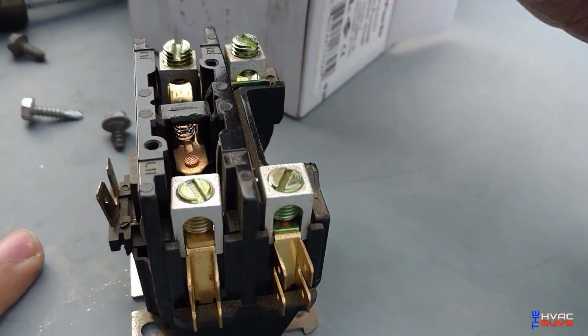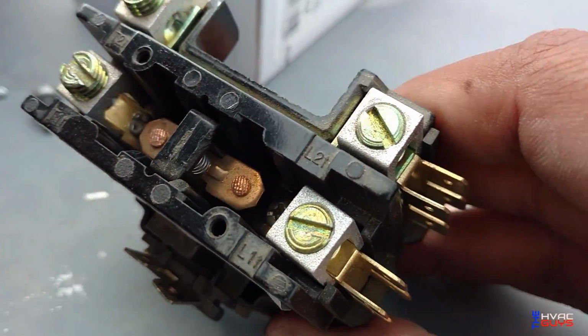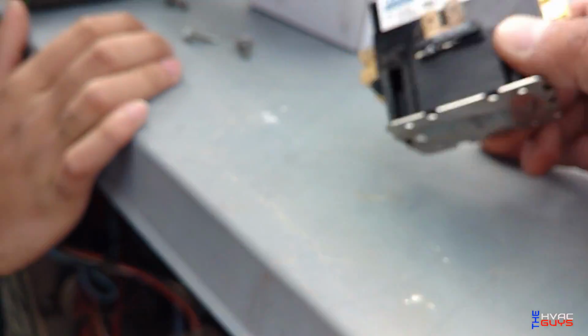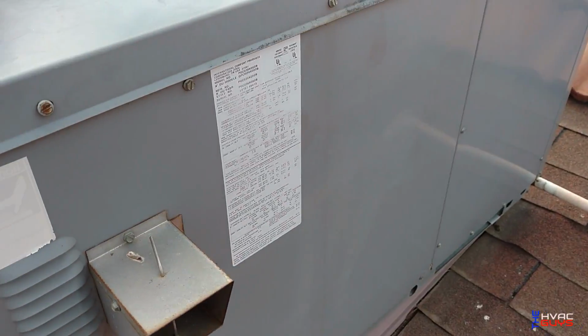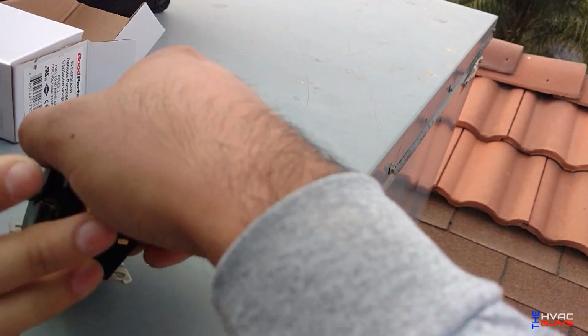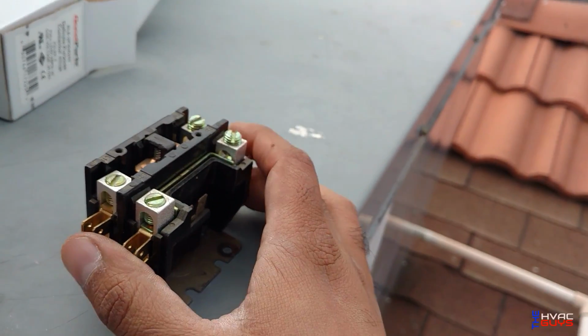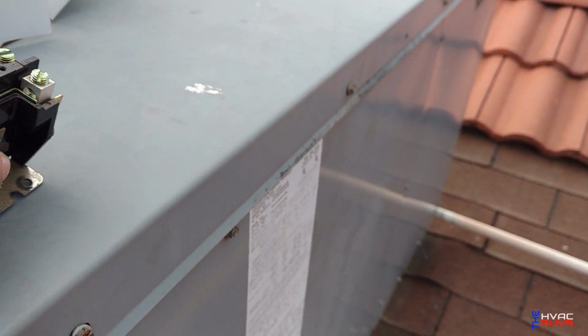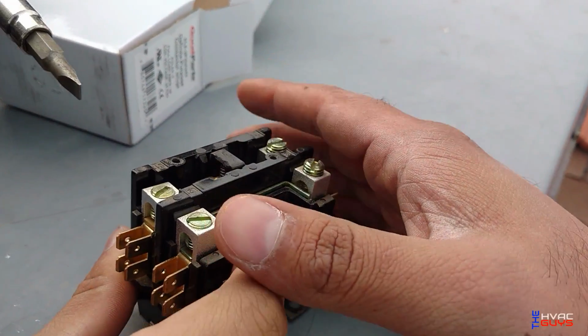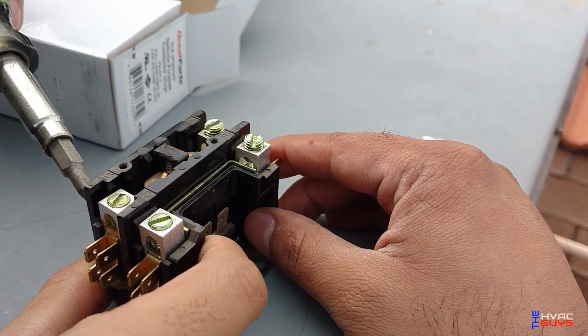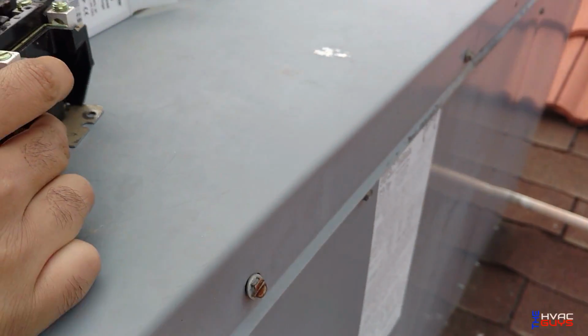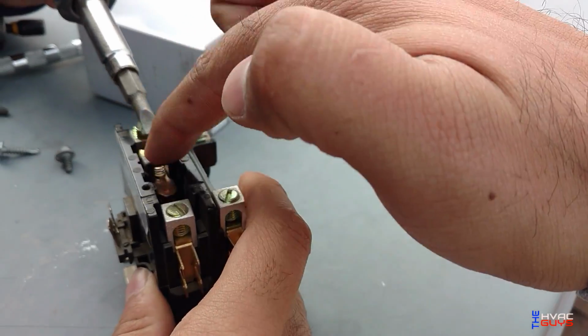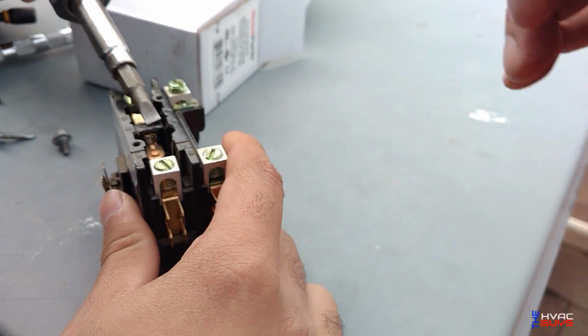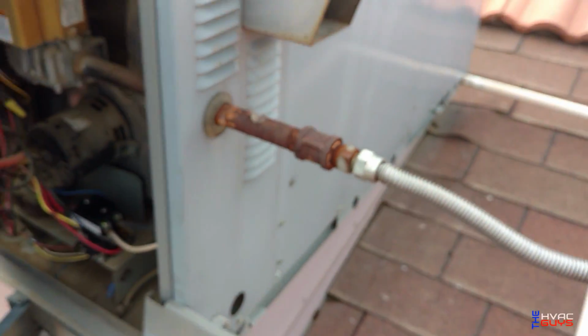Okay, so here's the old contactor. As you can see, it welded shut. The reason why this happens, sometimes it could be because the units are oversized. When they're oversized, the unit cools down right away, like in 5 minutes, it shuts off, and then the house gets hot again and it turns back on. That's what's called short cycling. So this eventually is gonna start - once we got it unstuck, it's gonna start getting stuck again because every time it turns on, it pulls a surge.